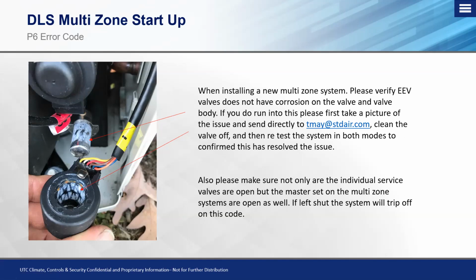unit. If you run into a situation, I always tell guys, if you have a P6 on your indoor unit, which is not labeled in the service manual, typically that correlates to a code at the outdoor unit, which is P1 high pressure or P2 low pressure. If you run into a situation where you have confirmed that a P6 is on the indoor or a P1 or P2 is on your outdoor, first verify that the charge is correct. Typically it's associated with a charge code with P2, which is low pressure.